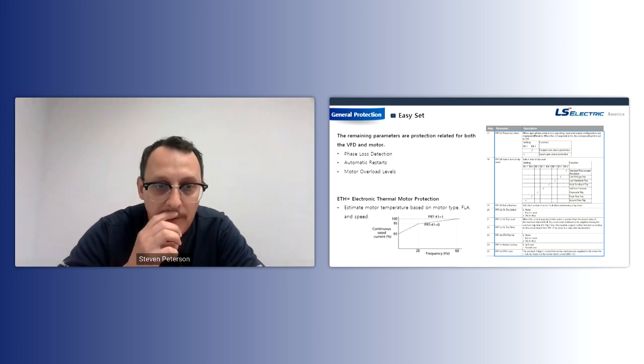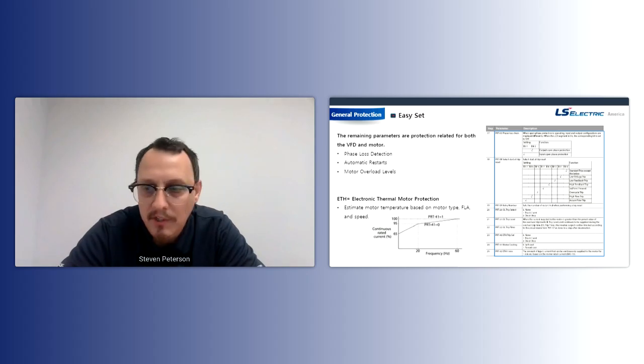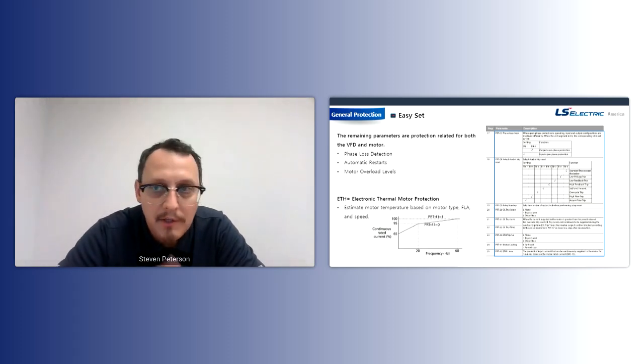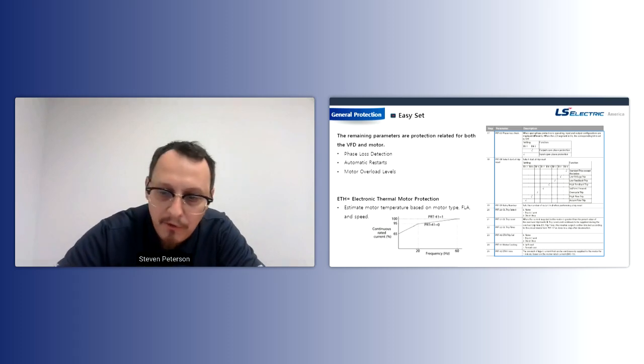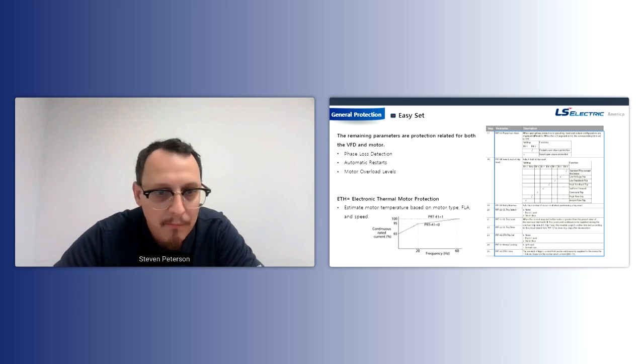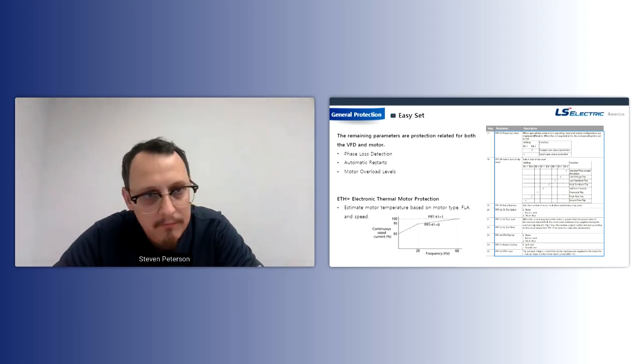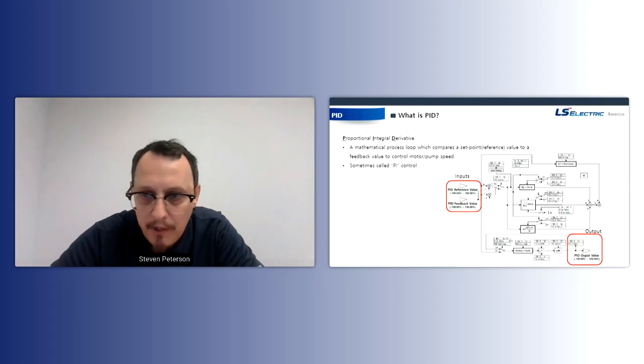This is a common trip we see, and people call us and ask, hey, why am I getting this ETH? Well, if you're running at a low speed and a high amperage, the drive's doing that to protect the motor. So the more you program into the drive, the smarter it is, and the better you're protecting everything, both the drive and the motor itself. So you don't need to be replacing anything from cooking a motor. So that was general stuff there.